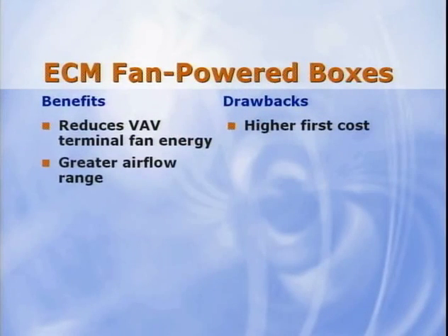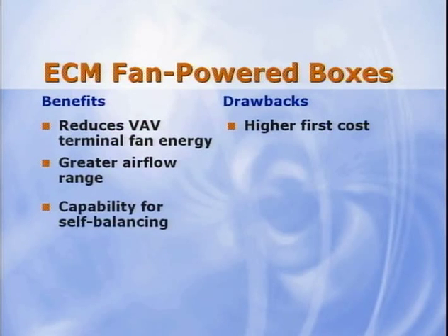The ECM allows for a greater airflow range for a given fan size. We saw this in the previous slide. If the usage of a zone is expected to change frequently, this ability to change supply airflow may avoid the need to replace the VAV box. An ECM is also capable of self-balancing to a desired airflow. This may eliminate additional balancing dampers or changes to downstream ductwork to ensure proper airflow.